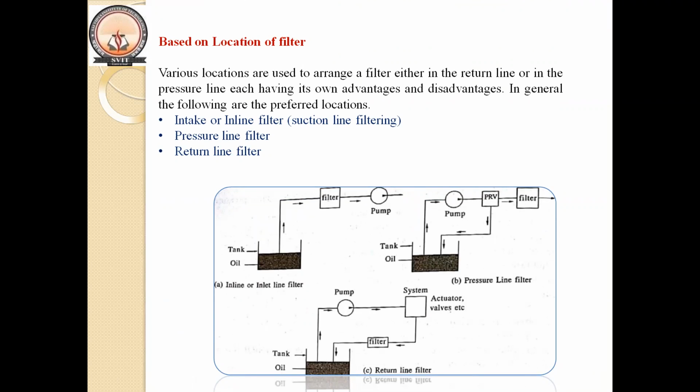The first diagram is the intake or inline filter. Here the filter is placed before the pump in order to protect the pump against contamination. But the disadvantage of the intake or inline filter is it may create a starvation in the pump. That is one of the disadvantages.